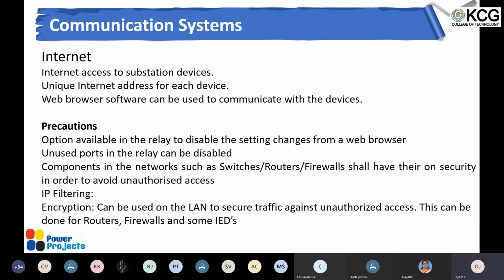Nowadays, any device can be connected directly to the internet. We can open a web browser and just put the address of that particular device, then you can open all the settings on the web browser directly. So this causes an issue also, like there is no sophisticated software required for changing any setting in the relay. Somebody can go to the relay, connect to it with a LAN cable or something, and just type the address of the relay. If they get that address through some other source, then anyone can change the settings. So that's a concern also. So generally, at the industry level, there is an option available in the relay to disable the setting changes from a web browser.